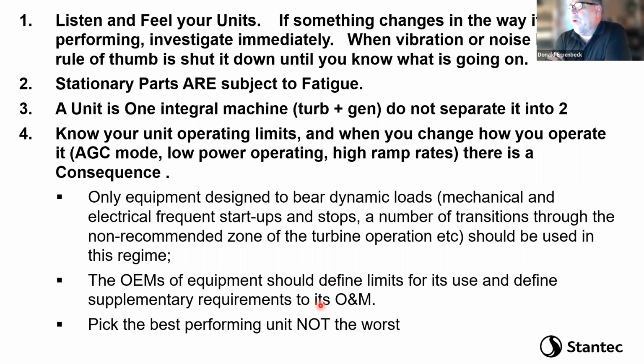A general rule of thumb is when vibration or noise doubles, you shut it down unless you know why. An increasing noise or vibration, okay, those things happen, but when you see a doubling of it, it's pretty much an automatic trigger that something has changed in a significant way.